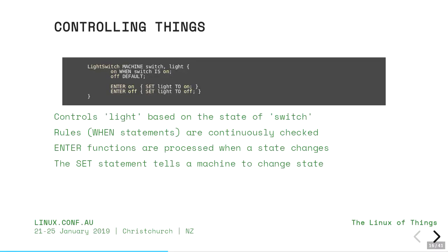Here is an example of a light. Lights have a switch, and we have a rule that says 'on when switch is on.' We turn the light on and stay in that state until somebody turns the switch off. The set commands in 'enter on' and 'enter off' actually turn the light on and off. I also have a concept called guards, which I use to protect against damage to machinery — extra code that forms a layer below, actually interfacing to the real hardware.